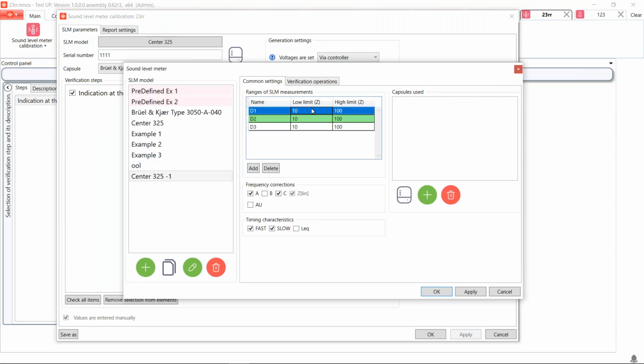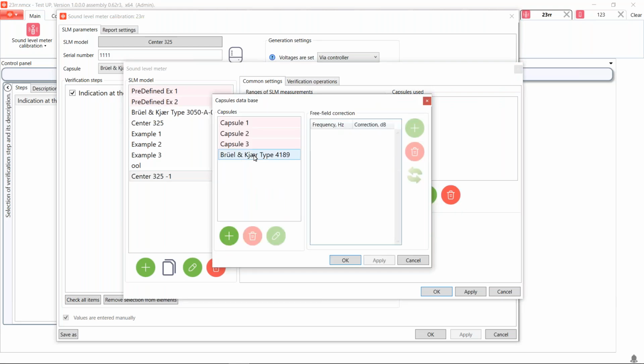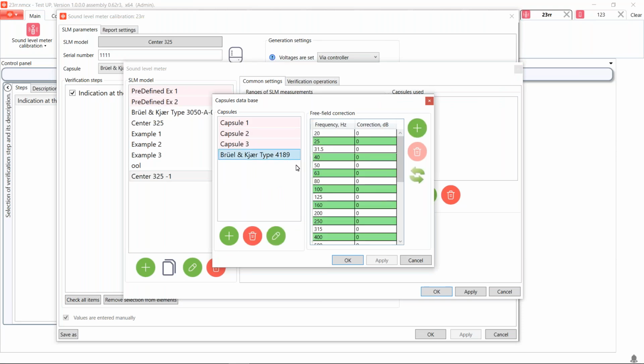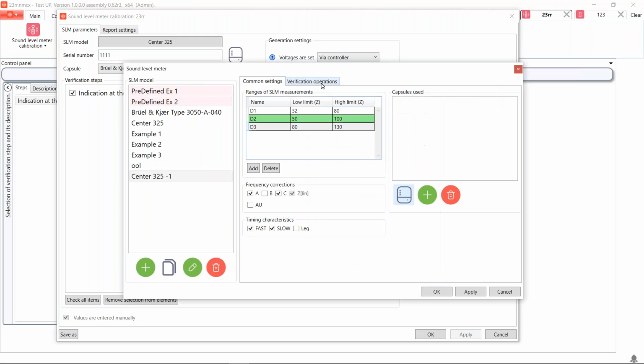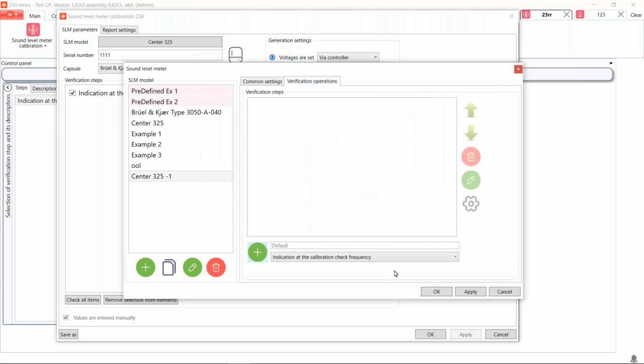So the low range starts from 32 and goes up to 80. Middle range from 50 up to 100. And the high range from 80 up to 130. After that, we need to enter the capsule. And here we will add Bruel & Kjaer type 4189. And next we open the verification operation.